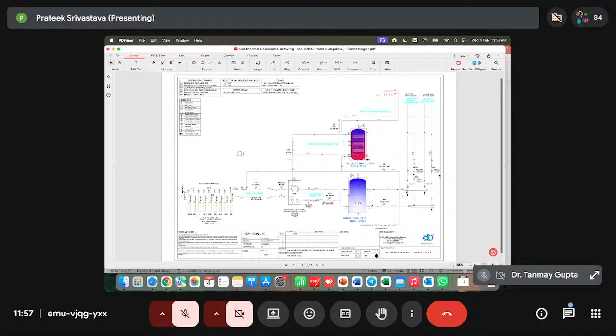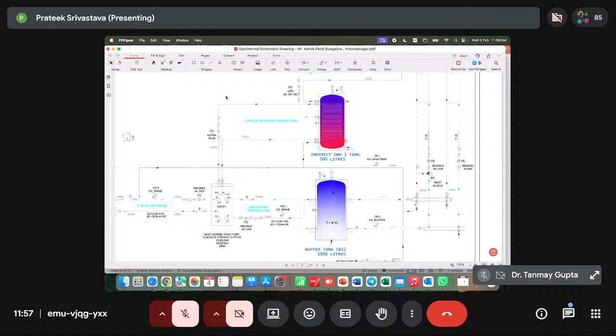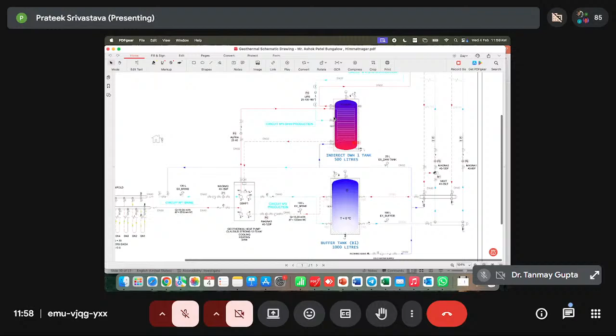Then when we come to the right hand side, these are two tanks. One tank is feeding the chilled water, and the temperature we are maintaining in this tank is 7 to 8 degrees Celsius. This tank feeds chilled water to the air conditioning system, to the radiant cooling system, and to the fan coil units. This machine also has a desuperheater. When we do the cooling, the heat comes here and heats the hot water in this tank, and this gives the hot water to the building. So this is the basic fundamental of this project.